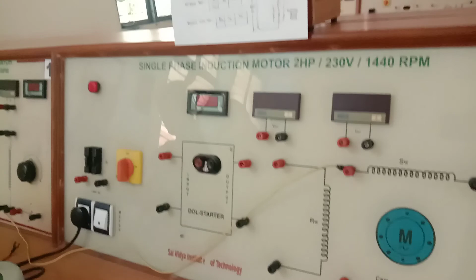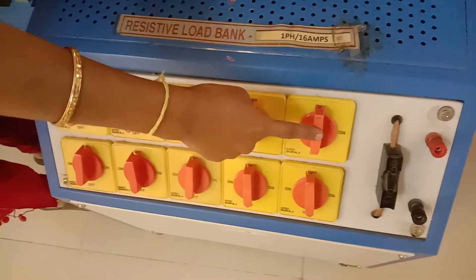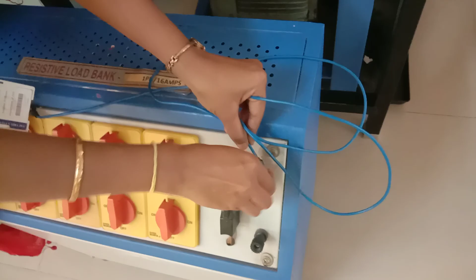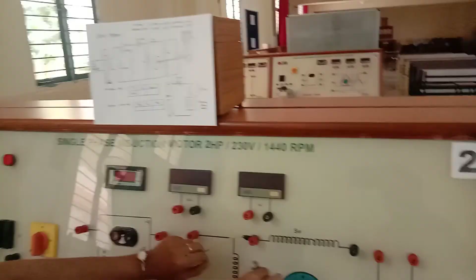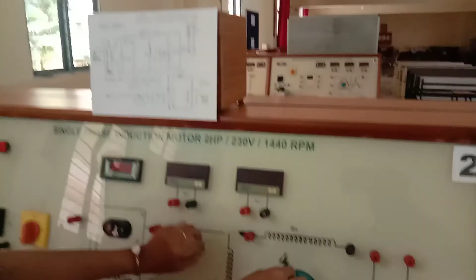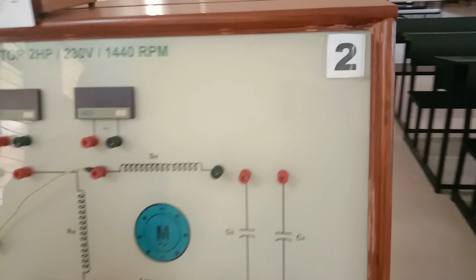So here this is the resistive bank load which you are going to use, which is of 16 ampere. In this case, the first 4 switches correspond to 1 amp each, and from the fifth switch onwards, each corresponds to 2 amperes. So this all will be 2 amperes, and the fifth switch is also included as 2 ampere. So let us connect this one end of this resistive load to one end of the stator winding.